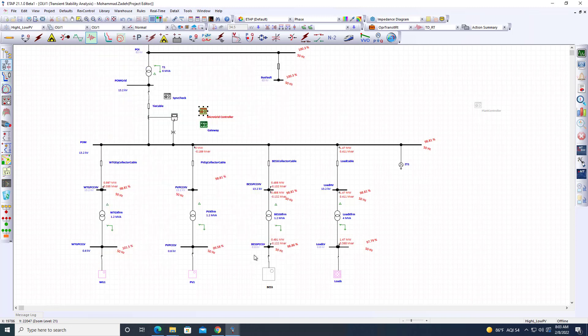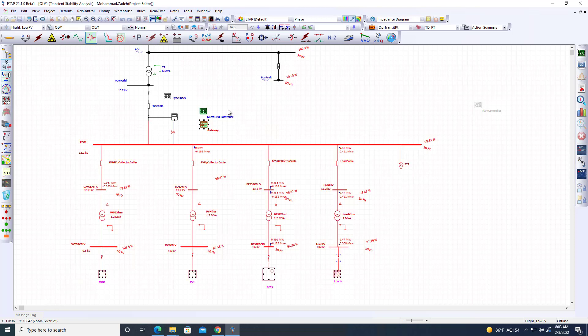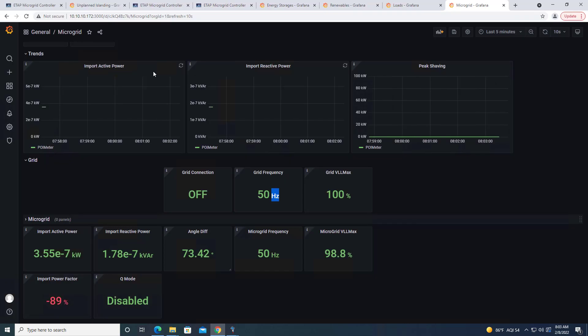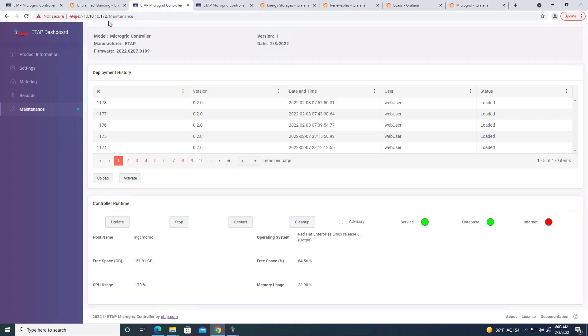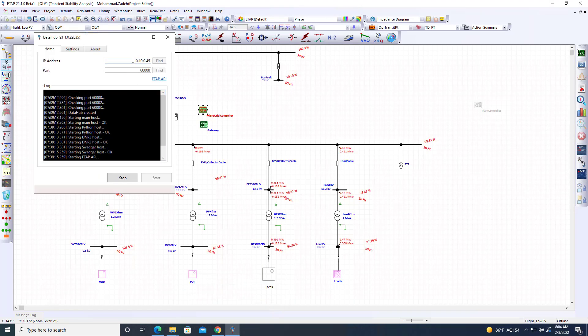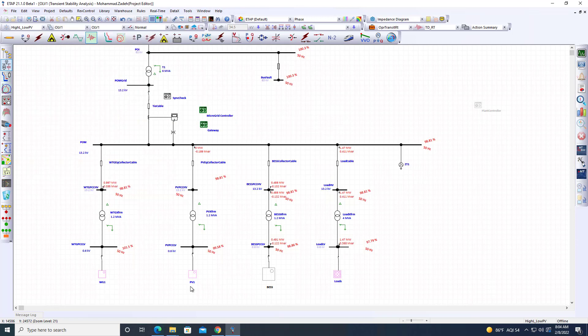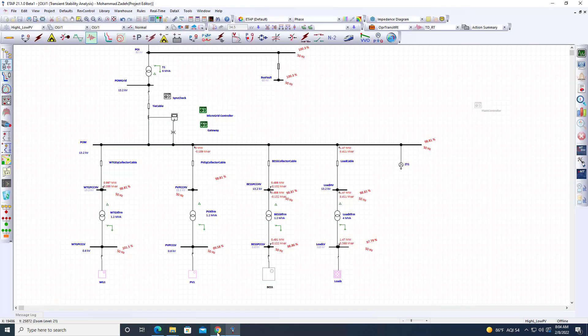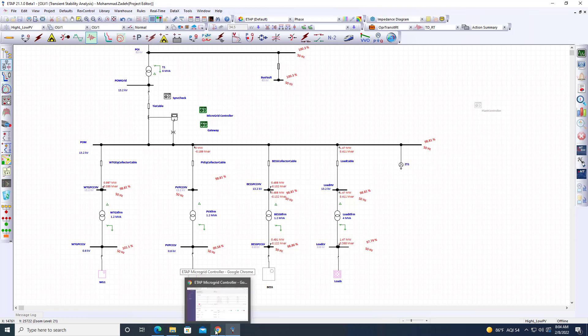Let's imagine I want to test this in real time with the real time digital simulator. The entire system is going to be modeled in the real time digital simulator, and then the microgrid controller is going to be hardware connected to the communication. Right now, I have my microgrid controller at the IP address of 10.10.10.172. This computer that we're working on right now is at the IP address of 10.10.10.45. ETAP has a DNP3 interface that can put the data out, all the measurements that microgrid needs. The microgrid controller hardware at this IP address has a DNP3 client that can grab those data, process them.